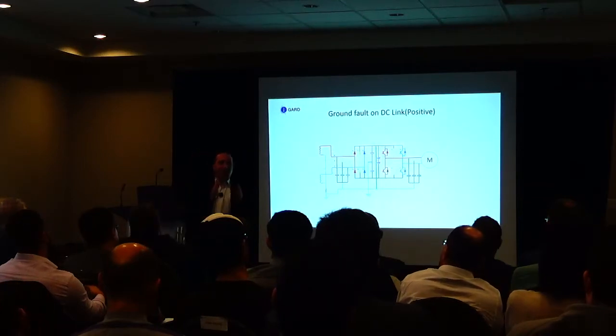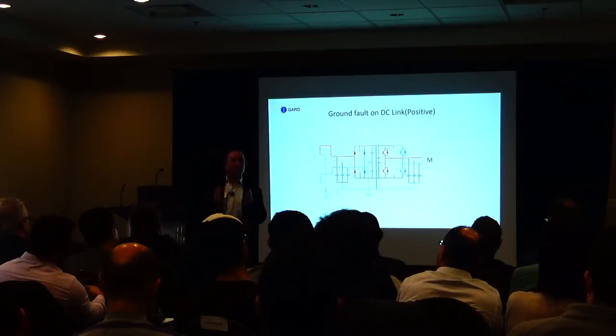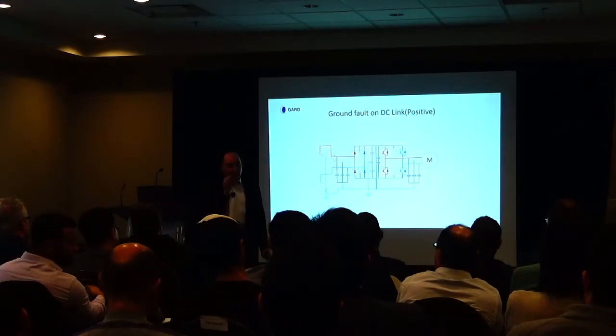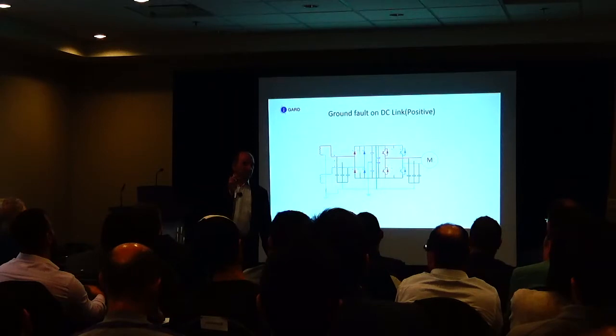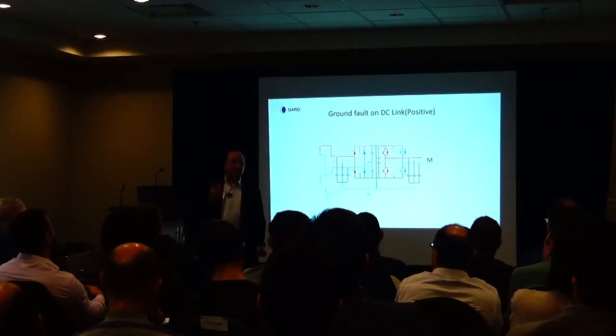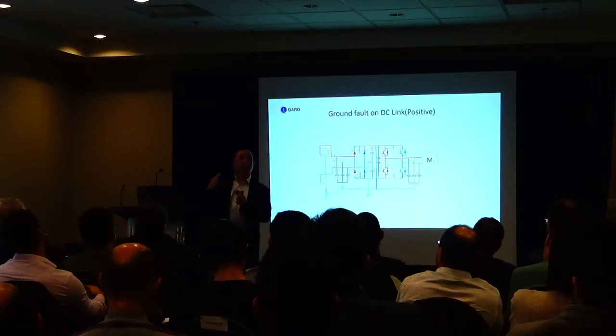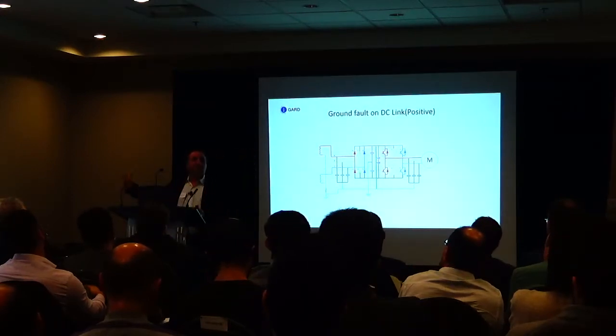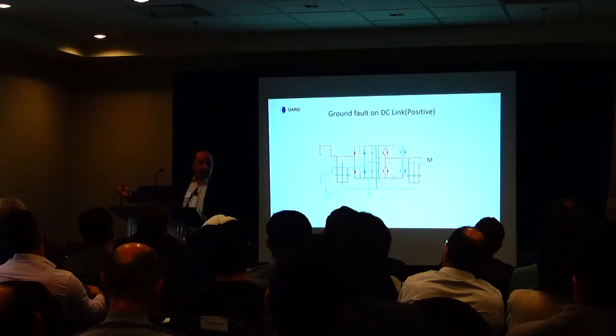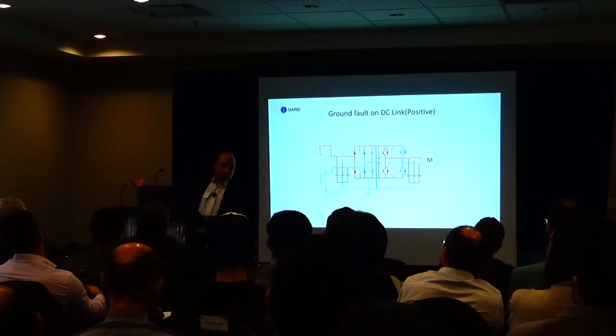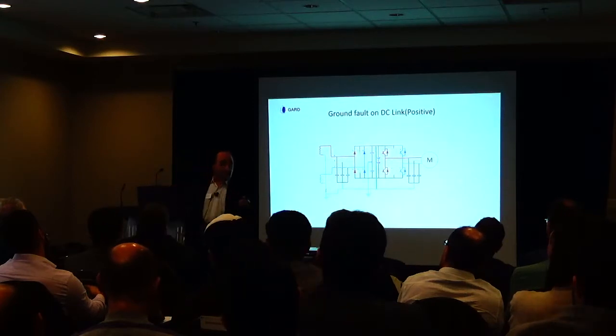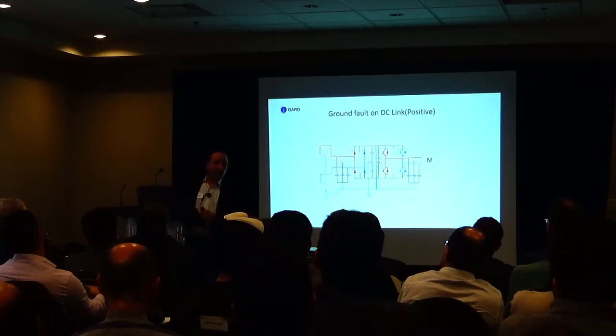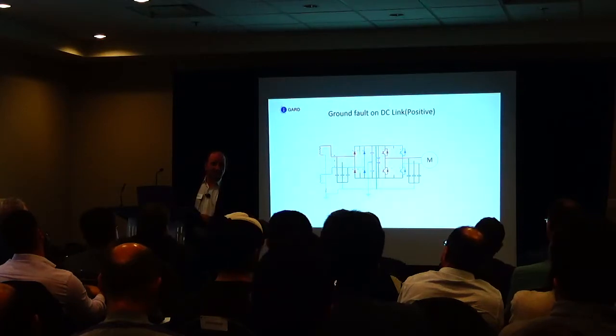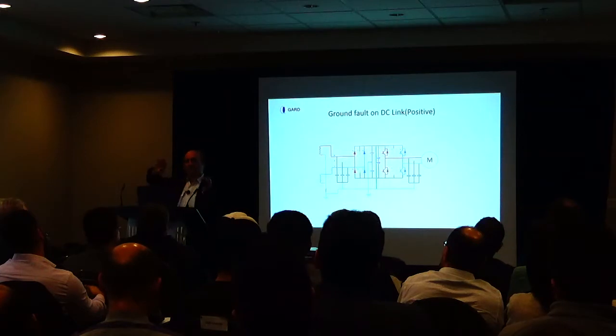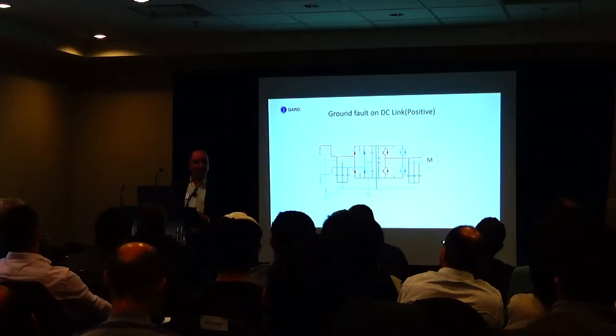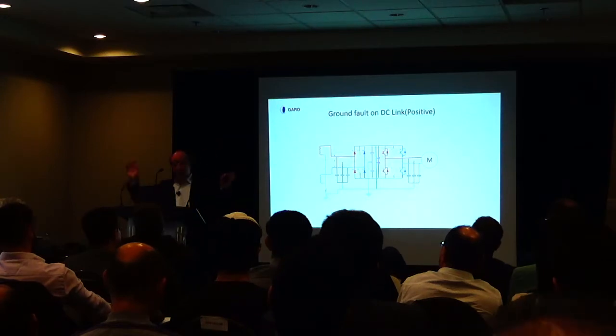Okay, let's look at it practically. If you had a variable frequency drive, how big is a DC bus? It's half an inch? A quarter inch? A terminal? How big is it? It's not very big. It's more practical that you're going to have a fault on the output of a variable frequency drive because that's where the motor is. Correct? So let's see what happens if you have a fault on the output at the motor on a variable frequency drive. What do you think is going to happen? Let's take a guess. What does this side of the room think? I'm going to tell you. You don't have to guess anymore.